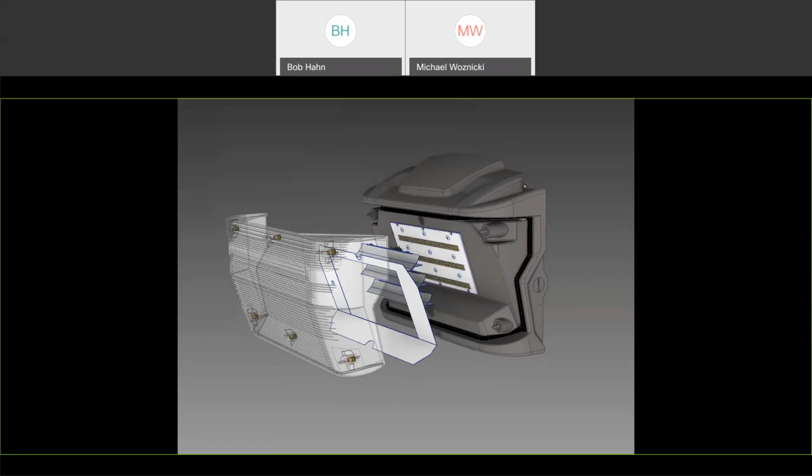But in order to meet DLC, the requirements state that the light coming from the fixture does not include any of the lumens that go above the 90-degree level. Those are discounted. And you can have no more than 10% of your total light output between 80 and 90 degrees. That prevents somebody from putting just a shield on top of the fixture. So a majority of your light output is underneath the 80-degree range and very uniformly spread. You can see the tilt here in the lens.